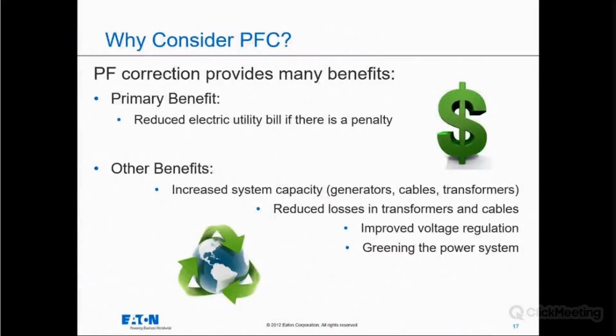So why would you consider power factor? Well, as we've shown, the number one reason is if your utility is penalizing you for poor power factor and you currently have poor power factor in your plant. But there are other benefits. As we just showed, you can use your system more efficiently. In the example we just showed, we lowered our system requirements from 125 kVA to 103. So we increased system capacity as we see here. So you'll increase capacity all the way through your system. If you're correcting at the motor, you would increase the capacity of your MCCs, your switchgear, and your transformer feeding the plant.